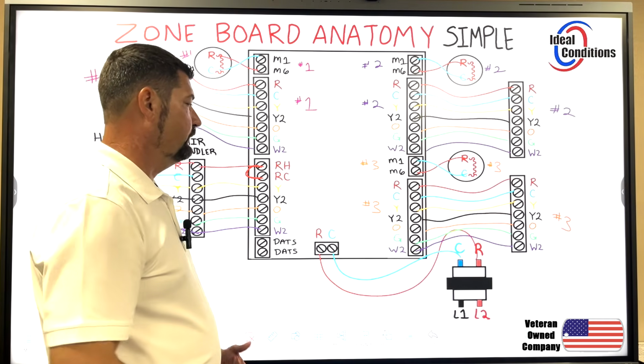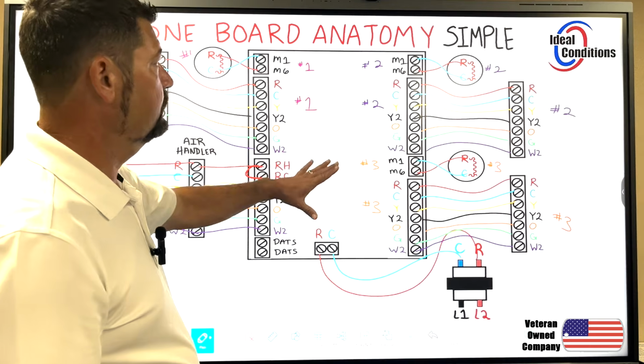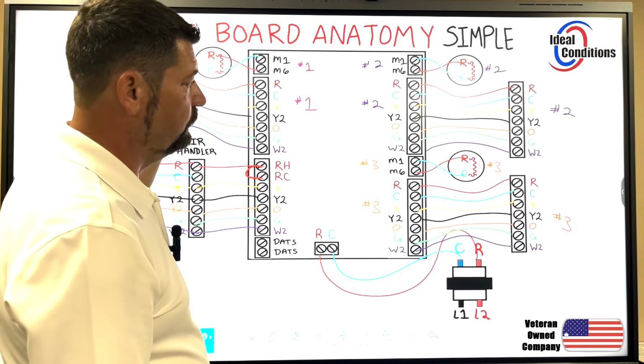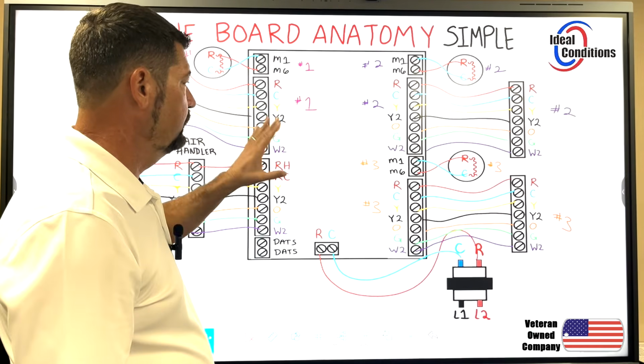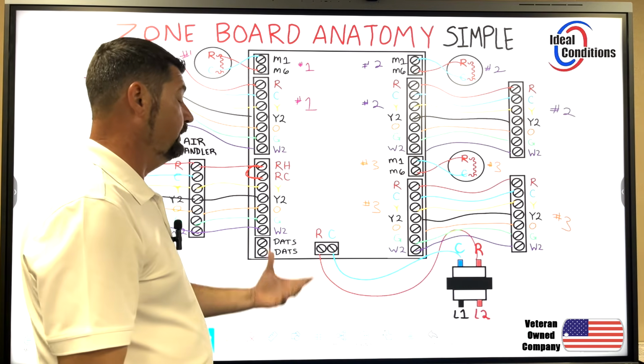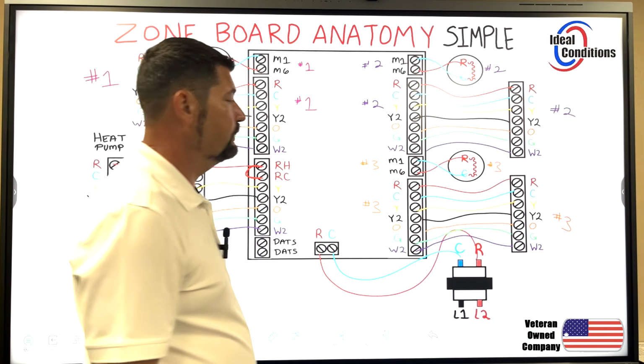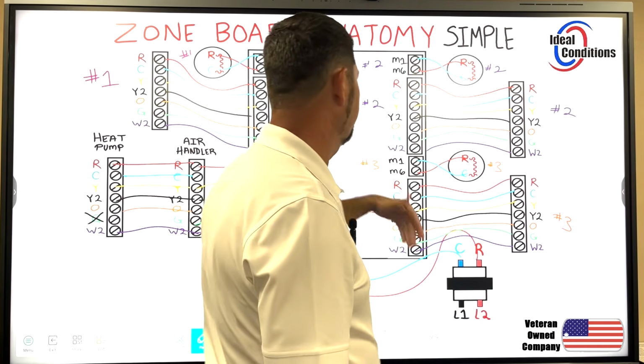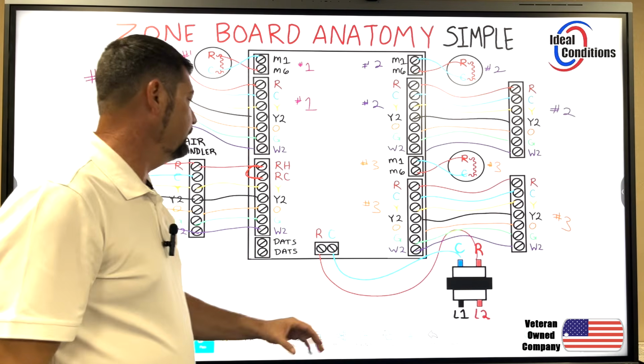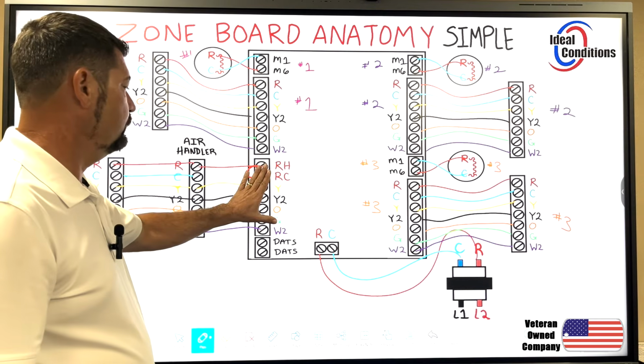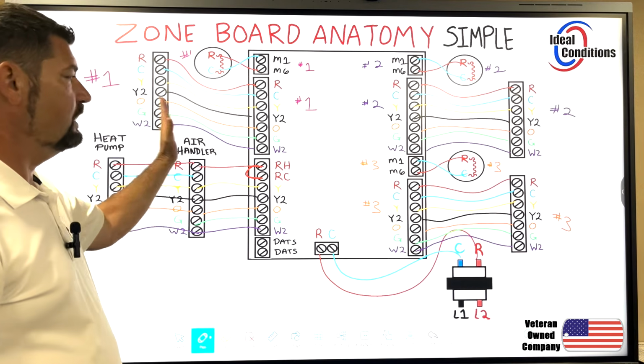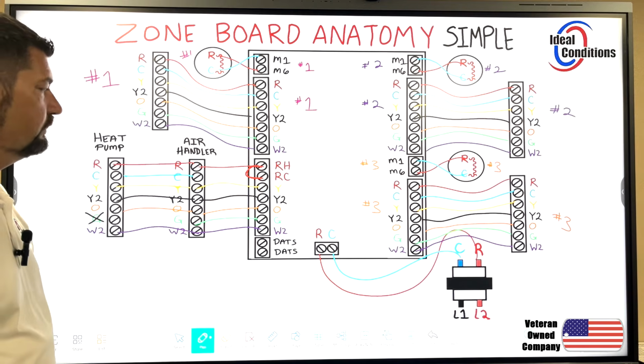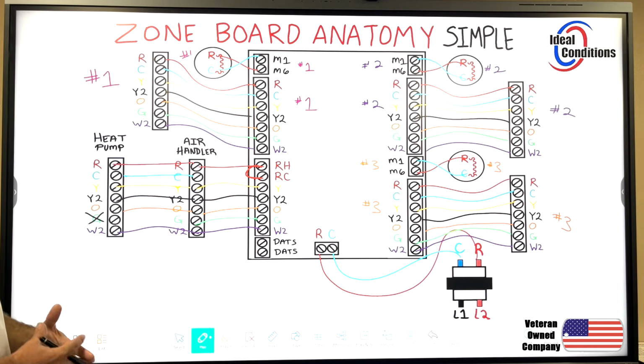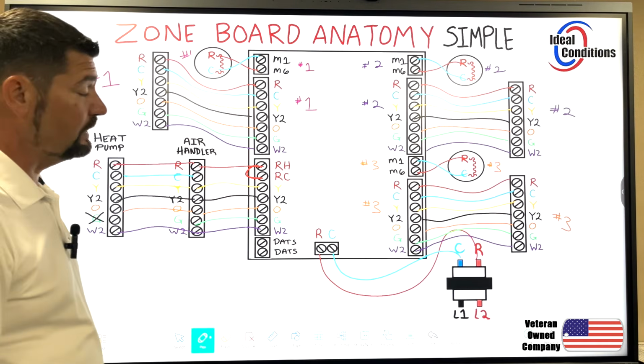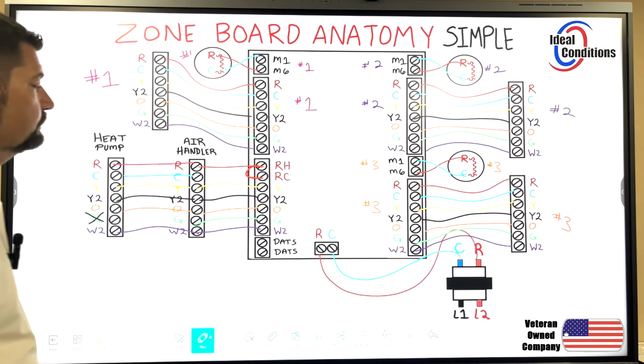I can't harp on enough about that signal flow. All you're doing on the anatomy here is extending a thermostat—you just have 3 of them, and your zone board is basically a thermostat, except it's not reading temperature. It takes information from the thermostats, and what it would normally do to your equipment block, it has an equipment block that it will release. So it's just an extension. Everything is redundant. It's a very simple thing—don't look at it and think it's too complicated to wire up, because it's not.